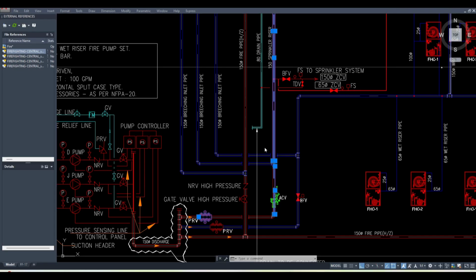This fire sprinkler system is designed to control the fire so that the fireman can come and start firefighting before it spreads to the other zone. So the main purpose of the fire sprinkler system is to contain the fire, not to eliminate it. It's not that powerful that it can completely suppress the fire of that zone. That's why the building is divided into zones, and in a particular zone we call it fire zoning.